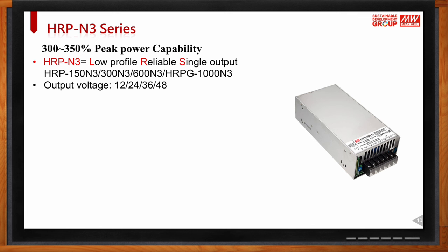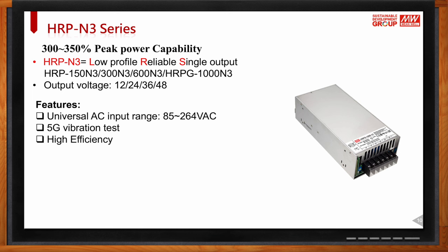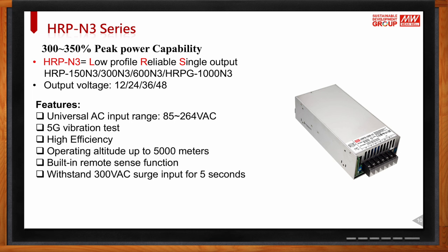Output voltages available are 12V, 24V, 36V, and 48V. One key feature of the HRP is universal AC input from 85V up to 264V — customers don't need to identify the input voltage for different countries, as the power supply auto-detects it. Some power supplies require a manual switch to select 120V or above 200V input, but the HRP handles this automatically. The HRP also features 5G vibration testing, so it can operate in vibrating environments, and achieves 94 to 95 percent efficiency.